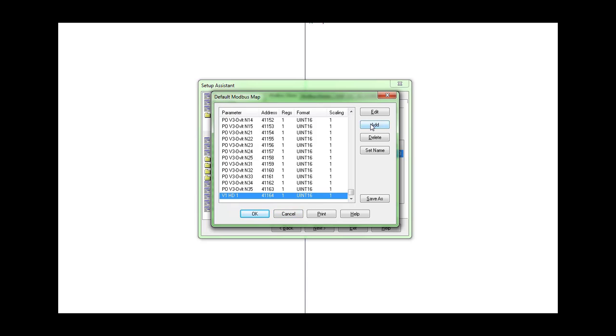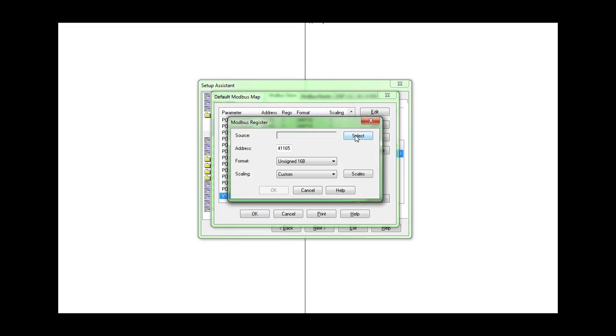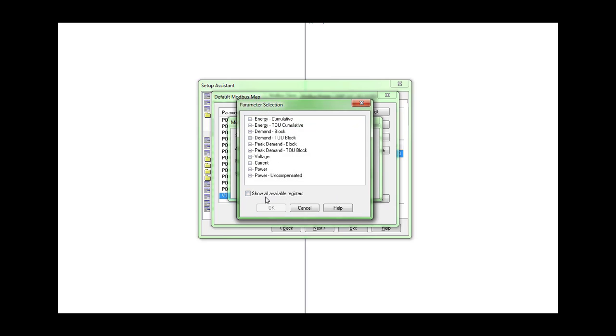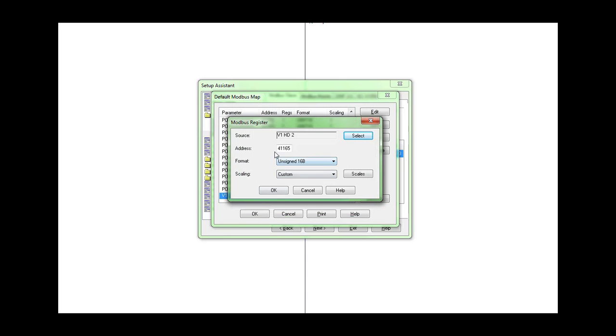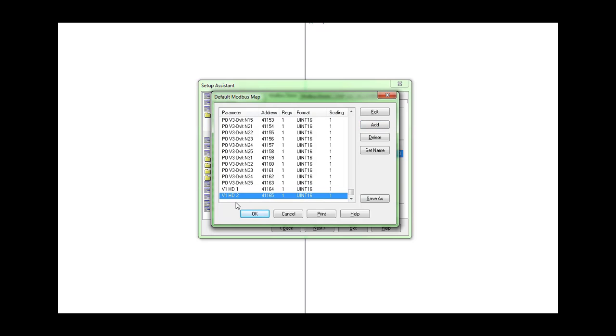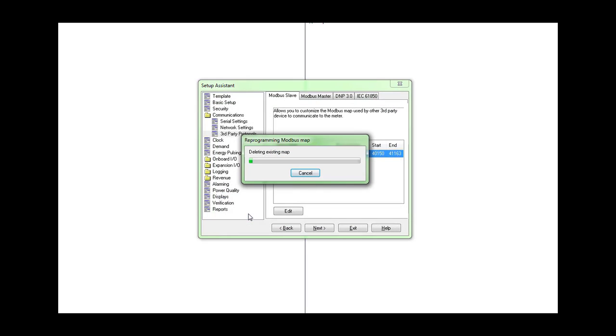So to repeat it, to be clear, I will add another value. I click on the Add button, then I search for the source again. Remember to check the box in order to show all available registers, and search for the harmonic module. Again, I pick the voltage for phase number 1, and now I select voltage 1, or phase 1, harmonic value number 2. Again, a new address is assigned for us, and we just click OK. So we are now seeing the summary of the map, and we just need to click OK.